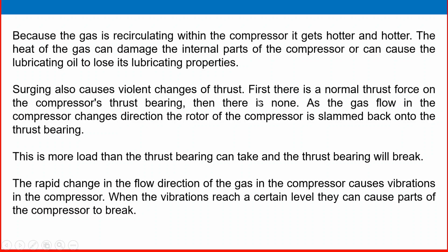We have already studied what thrust is. If you didn't watch that video on compressor internal parts, go through my previous videos to understand thrust, bearings, lubrication, etc. First, there is a normal thrust force on the compressor's thrust bearing. Then there is none. As the gas flow in the compressor changes direction, the rotor of the compressor is slammed back onto the thrust bearing. This is more load than the thrust bearing can take. The thrust bearing will break.